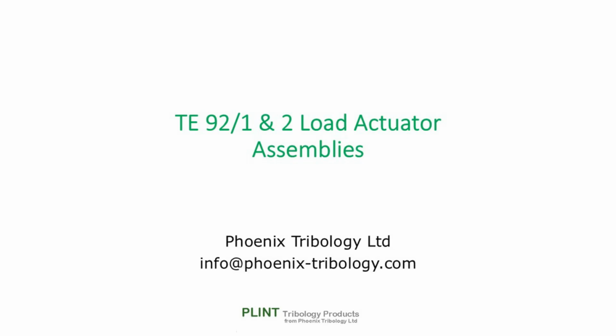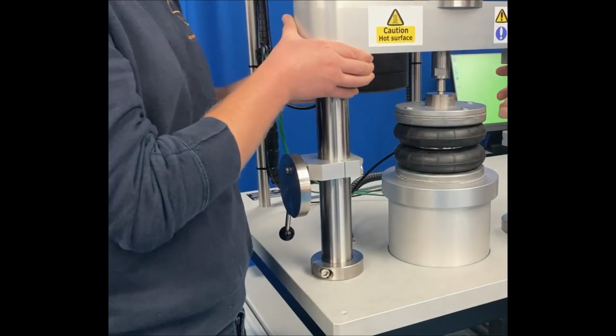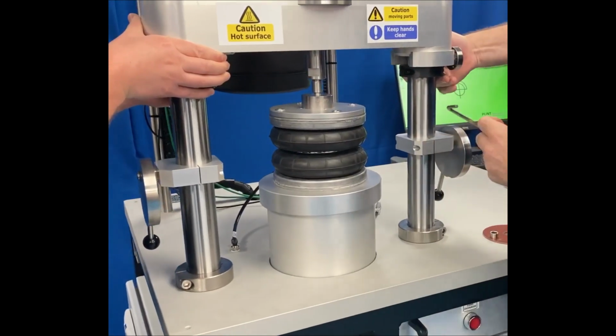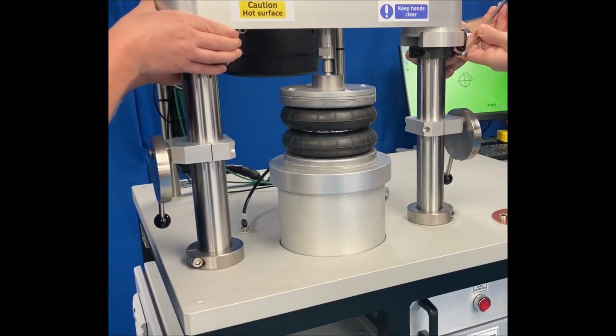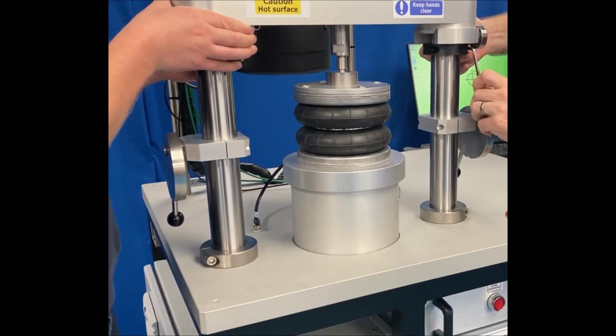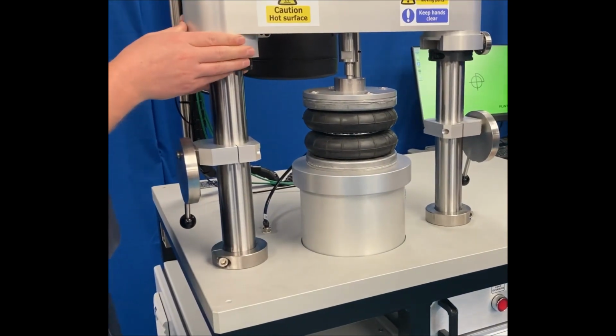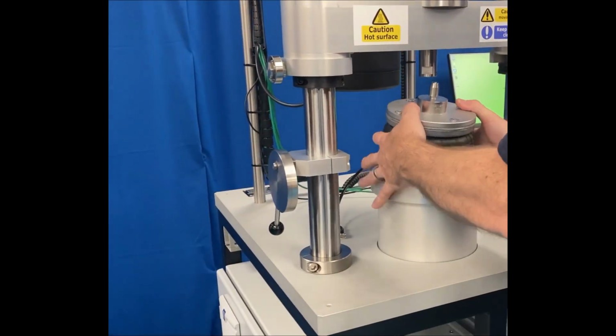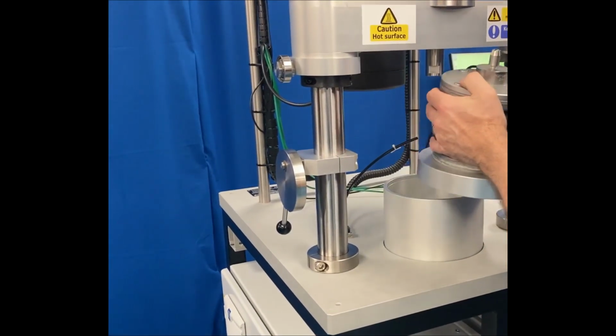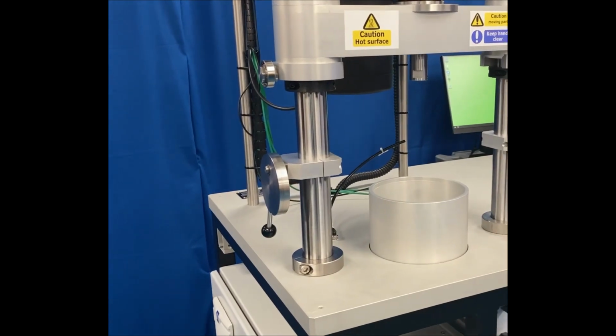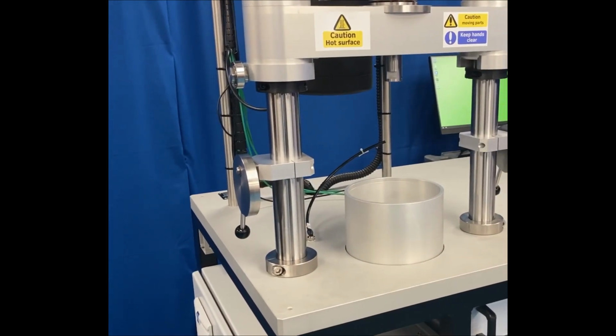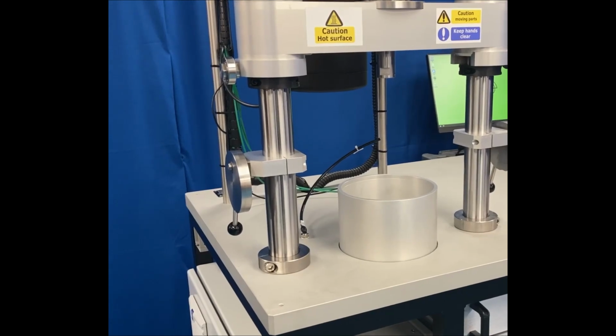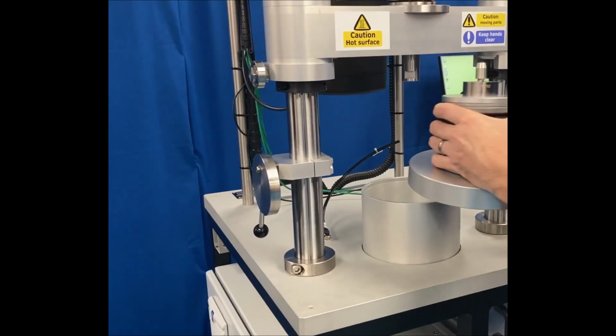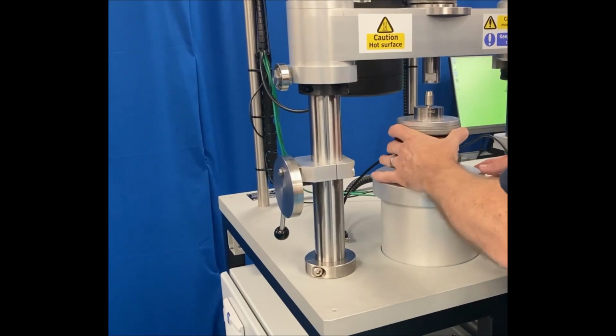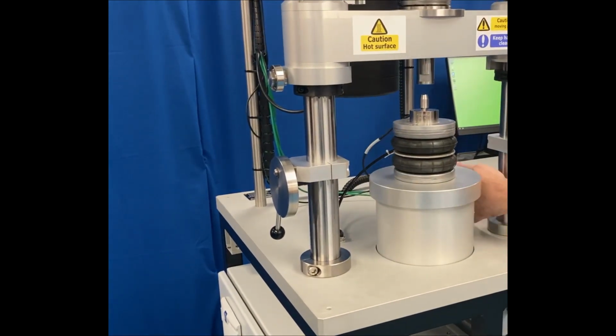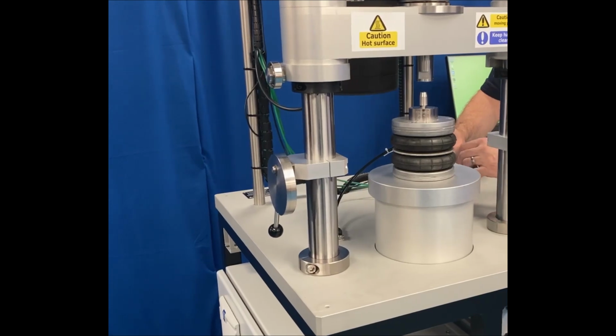On the machine, load is applied by servo-pneumatic bellows with force transducer feedback. Two sizes of bellows are provided, one giving a load range of up to 1,000 newtons and a higher capacity unit giving a load up to 10,000 newtons. Changing load range is a simple matter of removing one size of bellows and replacing it with the other.